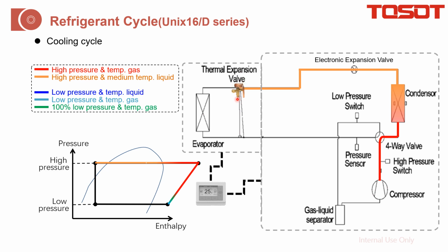So on site, actually, we don't require the insulation at the liquid pipe. So question number one, where is the liquid pipe? It's here, right? Because this is still a benefit to the cooling, we don't require insulation on the liquid pipe if this is only for cooling. And then the refrigerant will be metered here, from high pressure to low pressure, but still liquid. We'll go to here, right? Still liquid.